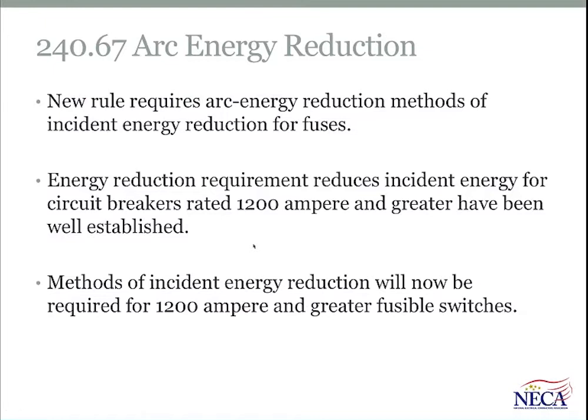Section 240.87 was new a couple of cycles back, and it provides arc energy reduction requirements in the NEC. That new section 240.87 was the first time in Article 240 where we saw prevention through design requirements added to the NEC. And in this case, you deal with larger equipment, equipment with larger capacities that's capable of producing higher incident energy levels.